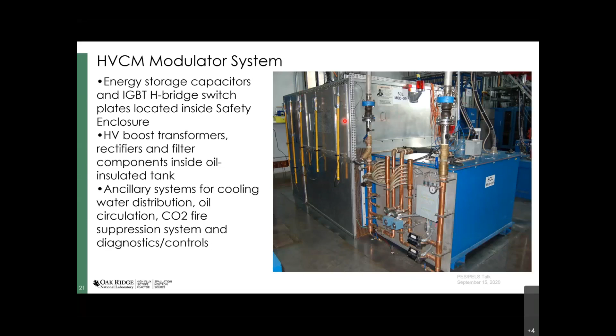The early control system we had was built by a company in Albuquerque, and it worked rather well, but it was limited in the modulation techniques available to control the IGBTs. Basically we only had pulse width modulation, pre-programmed to operate over a limited range, so it didn't meet our needs going forward. We also didn't own the intellectual property, which was problematic, and it was limited in the number of diagnostics available.